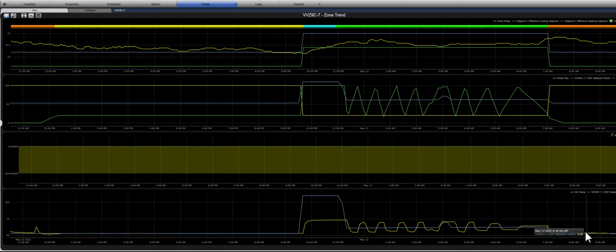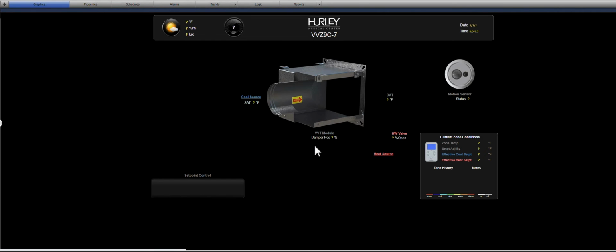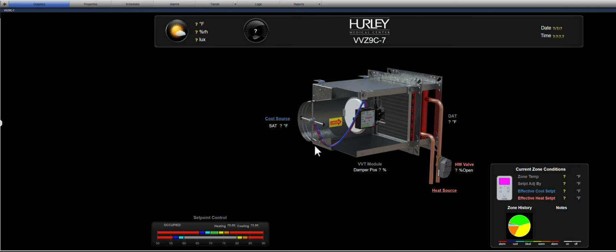So the machine controls very, very well in the cooling, very aggressively, maybe a little bit more aggressively than on the heating side. That's just the way the system is tuned right now. So we can make minor, very little adjustments to change that. So now we're in the orange zone, and if we look at the graphic, we can see that for quite a while we've been basically in that orange zone. We're down to 72.9. We've got a ways to go to 71.